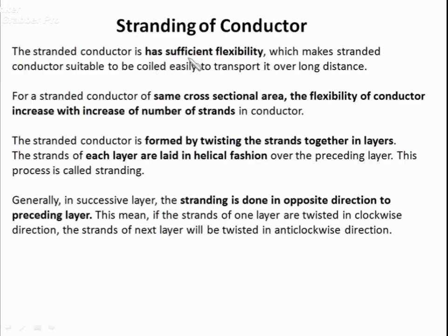Among other benefits, stranding of conductors increases flexibility, which makes a stranded conductor suitable to be coiled and easily transported. For a stranded conductor of the same cross-sectional area, flexibility increases with an increase in number of strands. The stranded conductor is formed by twisting strands together in a helical fashion; stranding is done in the opposite direction to the preceding layer.